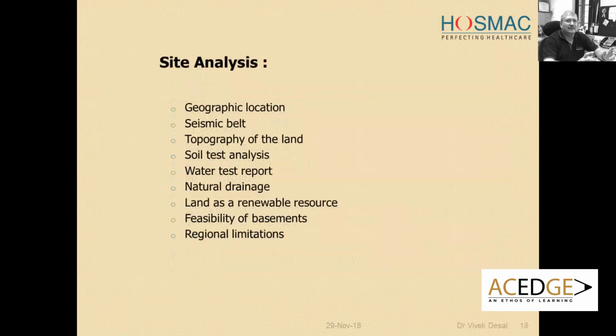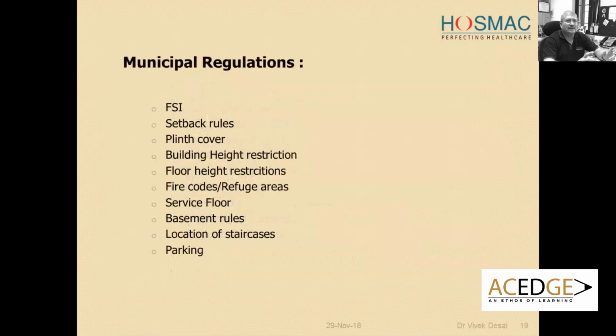These are other things that we generally do: seismic belt, topography, soil test, and all of that. I'm not going to deal much with that. You need to understand that hospital buildings need higher floor heights, because we are centrally air conditioned, and nowadays the government is not allowing flat slab designs for public utility buildings like hospitals. So you need to go with a beam slab, and that means that air conditioning will go below the beam. So we need about 4.2 meter height for hospital buildings, which in residential will generally be 3.3 or 3.6.